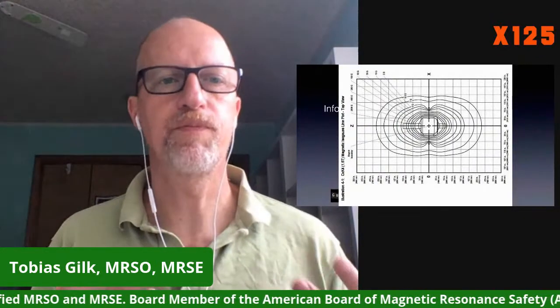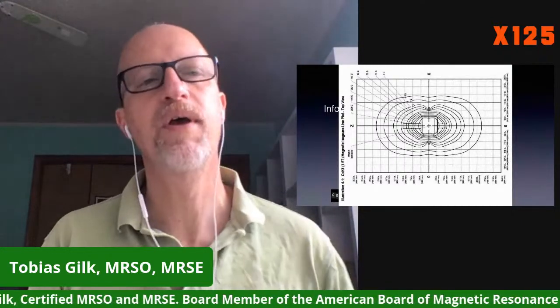On here, if you tilt your head sideways, you can see we have labeled the 5 Gauss, 10 Gauss, different static magnetic field values. The furthest one out is the 0.5 Gauss. Essentially that's atmospheric levels. That's the point at which we really can't discern static field originating from the MRI versus the Earth's own static magnetic field. So this is field strength alone.